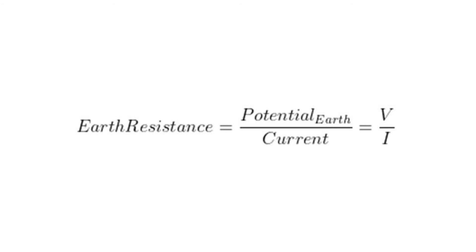And the formula is: Earth resistance equals the potential to Earth over current, or simply V over I, where potential to Earth is the measured voltage between the voltage spike.